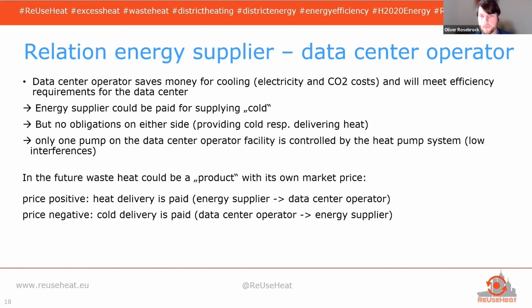On the other hand, they have no obligation to deliver the heat to the heat pump either. So if there's, for whatever reason, problems on our side or on the data center side, there's no obligation and no additional cost, no contractual fines or whatever if there's no delivery or providing on our side or on the data center side. As I said, only the one pump on the data center is controlled by the heat system, so we have very few interferences between both systems, which is quite a good thing.